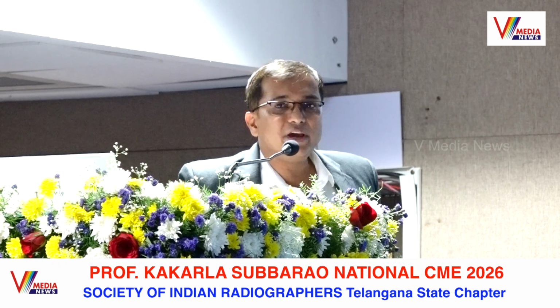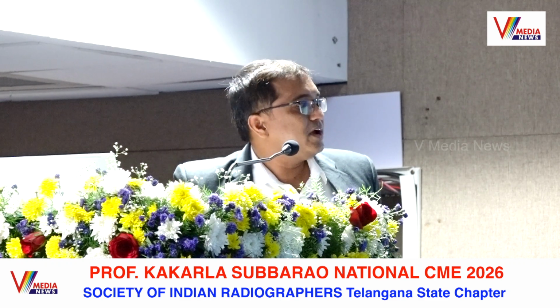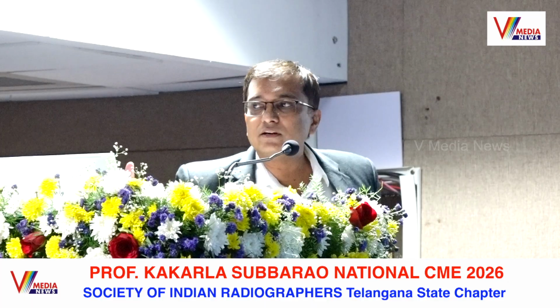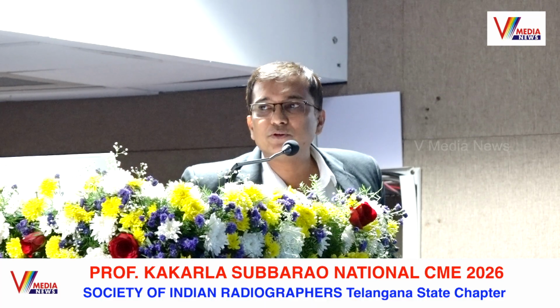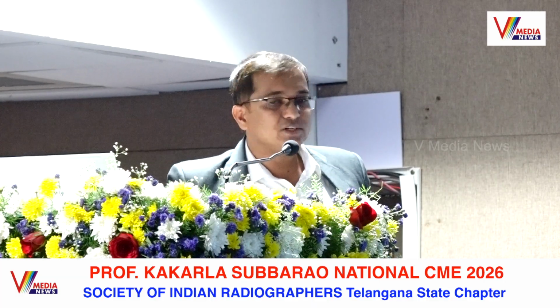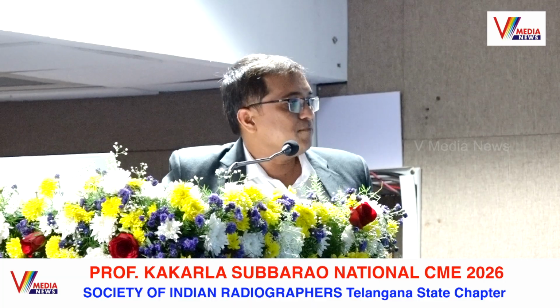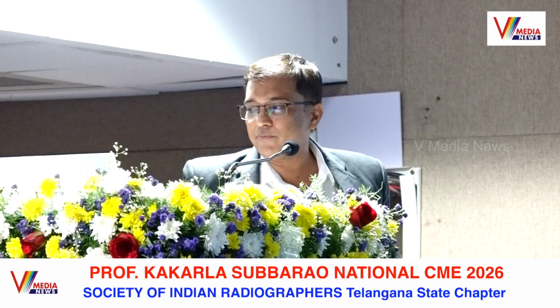So what is QA as per the AERB? QA, as I told you already, means whatever specific kV and mAs the equipment should give, that much only it should give. It should not give less or more than that. So how frequently should it be carried out? It is compulsory at least once in 2 years. Every 2 years you have to do the QA of the radiology equipment.